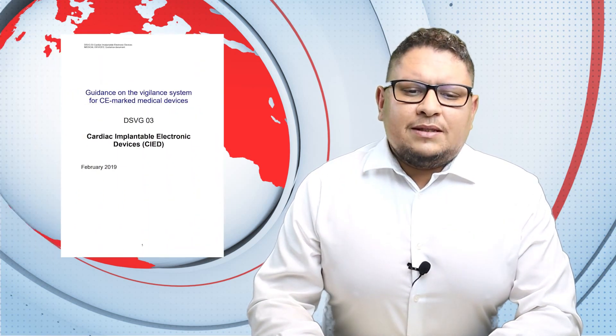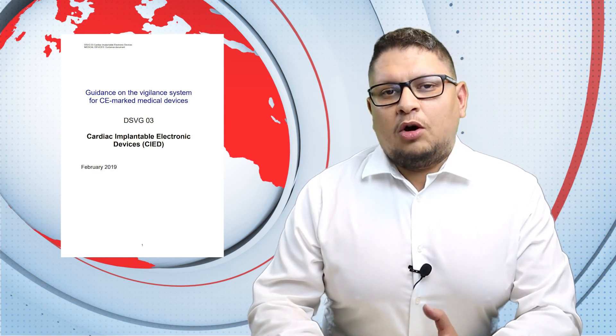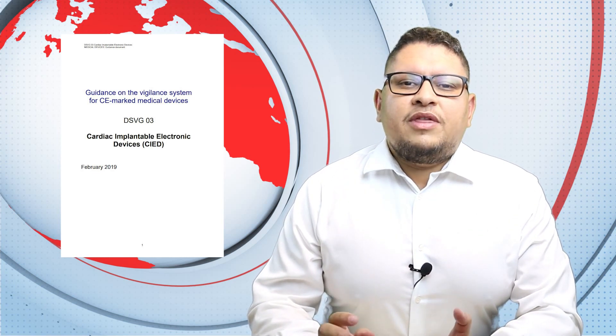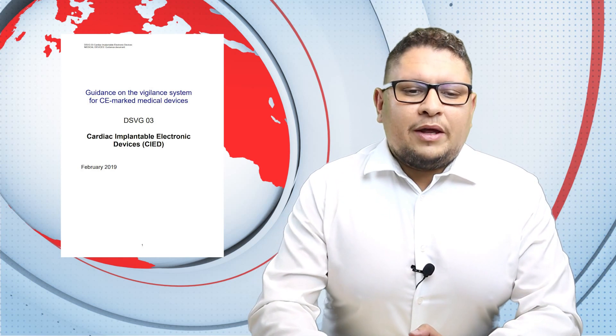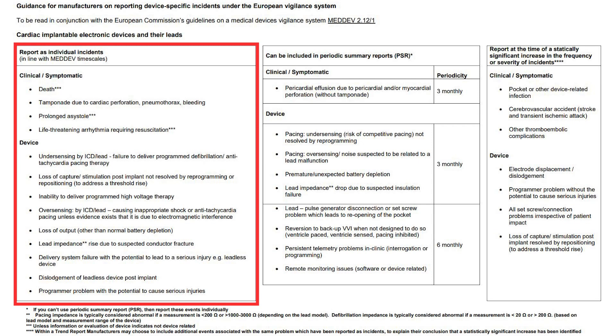Let's talk now about cardiac implantable electronic devices. This is called CIED, and the EU Commission issued a guidance for vigilance system reporting. Mainly, this guidance is helping you if you have this type of device, helping you to define when an incident should be reportable. There are three columns mainly where they talk specifically about incidents reported individually, such as death or prolonged asystole.